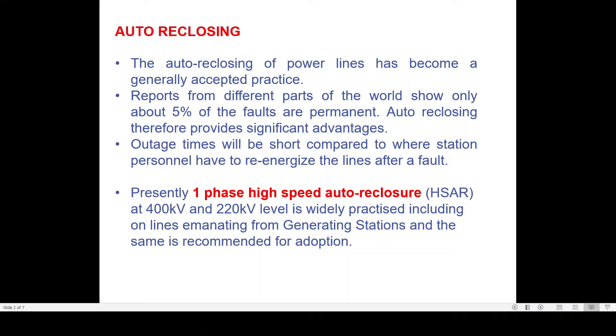In case of single phase autoreclosure, suppose there is a fault in R phase to ground. Your distance protection relay will issue a tripping command to the R phase circuit breaker poles and simultaneously send a signal to the autoreclosure relay called AR initiation. After a sufficient time interval — the dead time — the autoreclosure relay issues a closing command. If there is no fault, the breaker closes, completing the first stage. Then the breaker waits for the reclaim time, about 20 to 25 seconds. If a fault occurs within the reclaim time, the relay immediately issues a three phase trip command and the breaker goes into lockout.